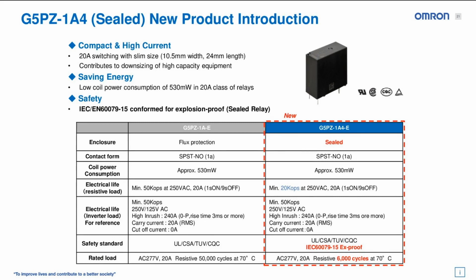It allows for highly dense boards to be developed, side-by-side relays. It saves in energy because it is a 530 milliwatt coil in a 20 amp class of relays, which is relatively low. And then, of course, it is conformed to the IEC rating for explosion proof. So the main things to note about this relay is that it is sealed. It is 1form-A for open-close switching.